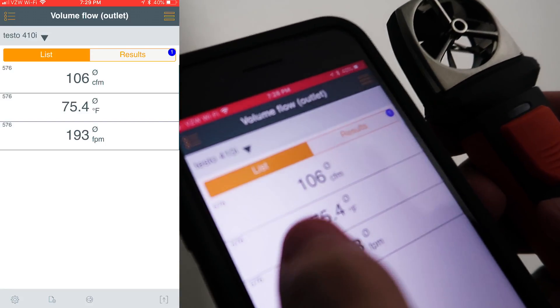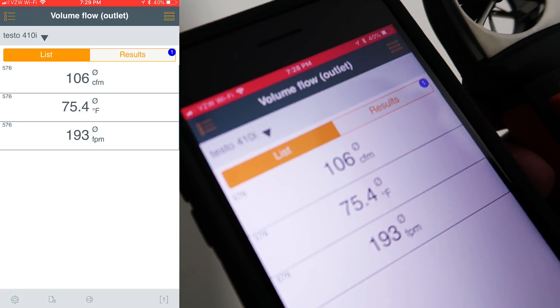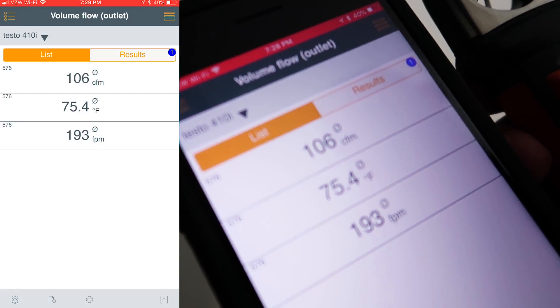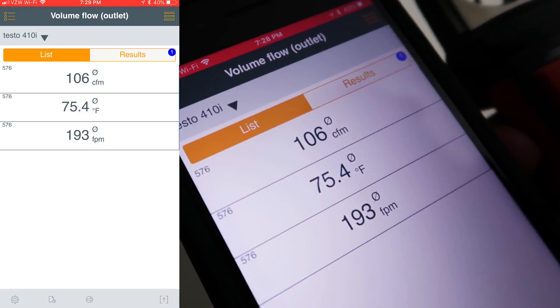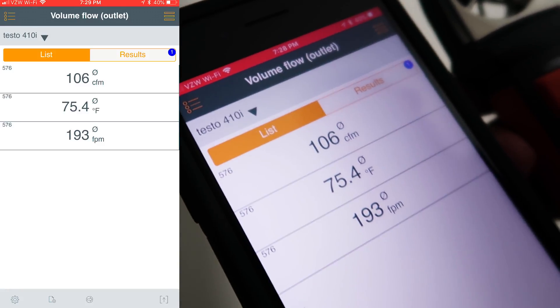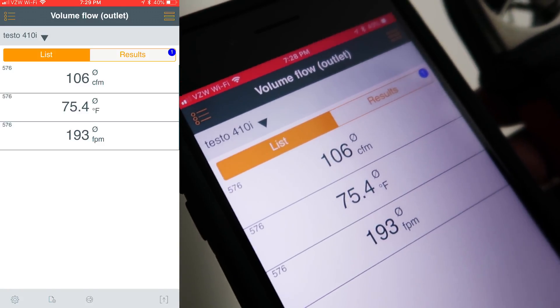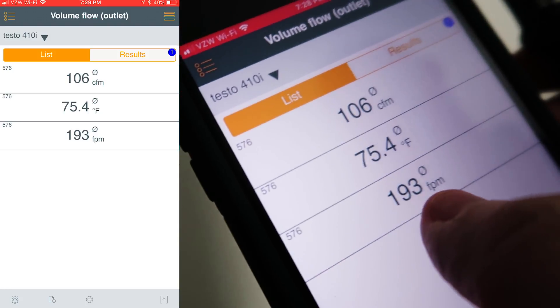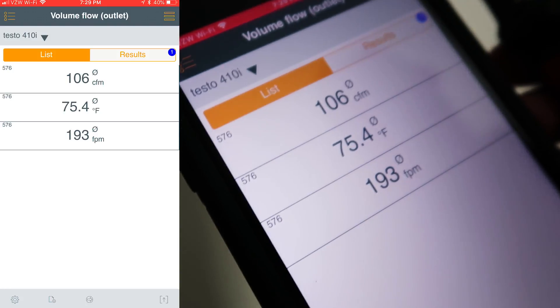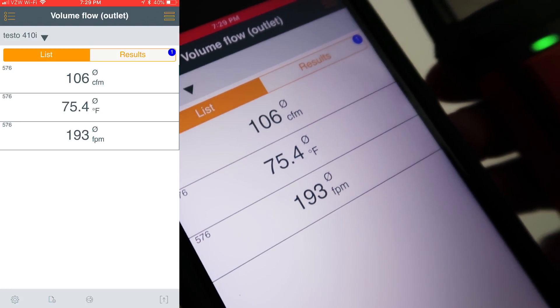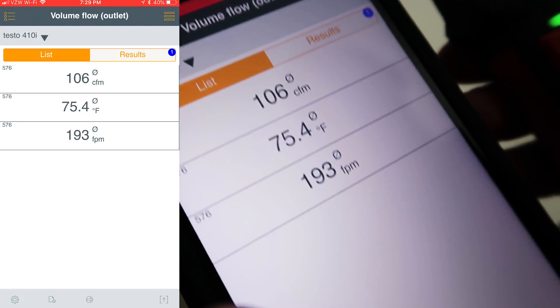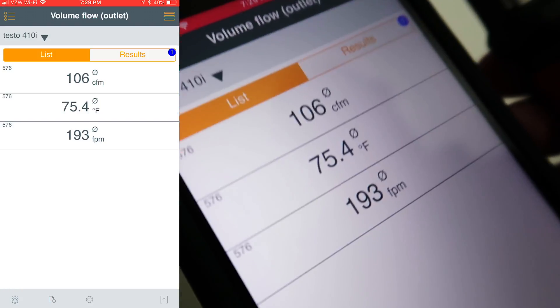You can see here that we have an average of 106 CFM. But again, in order to get that, you would have to know quite a bit about your vent. We do know that my average velocity is 193 feet per minute — that's pretty low.